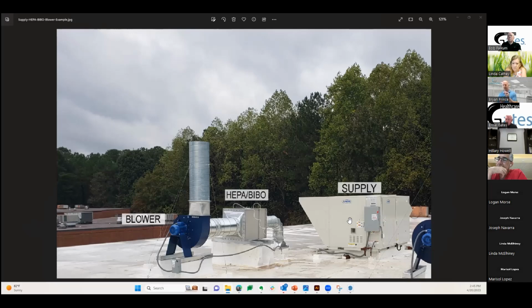So they'll actually go to their equipment vendors and say, I need it to do 68F at 60% RH. Happens every single time. And what ultimately happens is the system fails, because it was not designed to go below those points. They designed and engineered it to the lowest common denominator. I need to design it to what real life activity is.